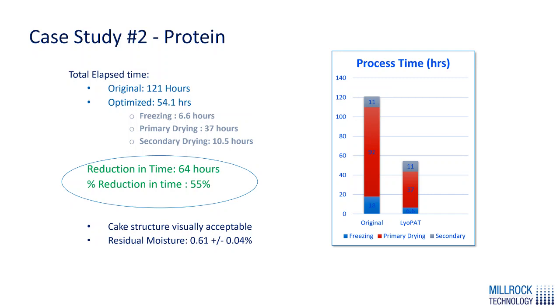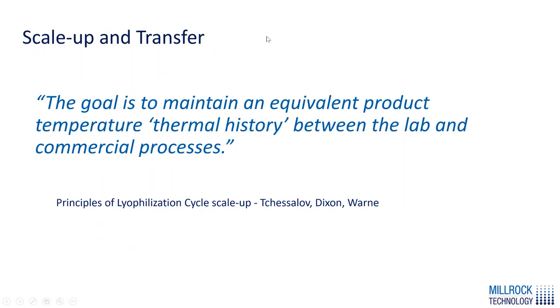Case two is with an actual protein — a 21 mL fill in a 50 mL vial. The original process was developed using an older technology from another company, producing a very conservative run of about 121 hours. We then implemented controlled nucleation, controlled heat flow, and auto-dry on this particular cycle and reduced the cycle to 54 hours. This is a 55% reduction in total process time, and it gave us a cake structure that was visually acceptable with an acceptable residual moisture content.